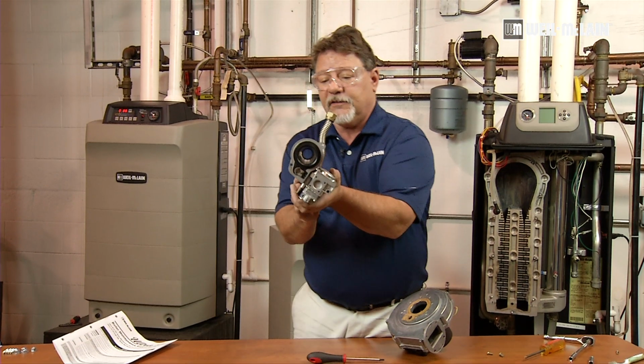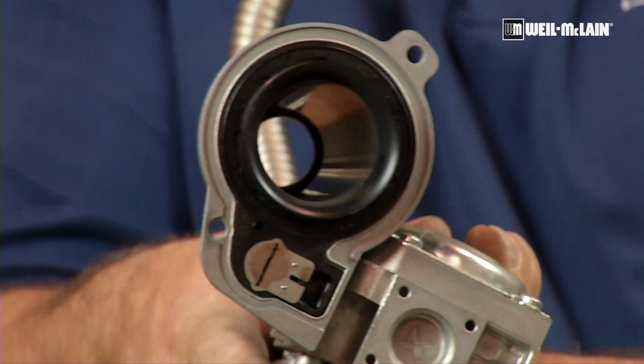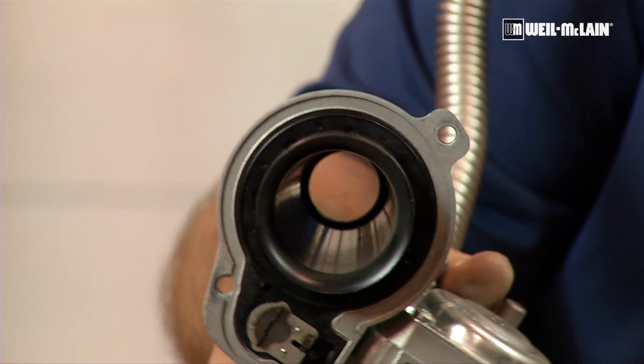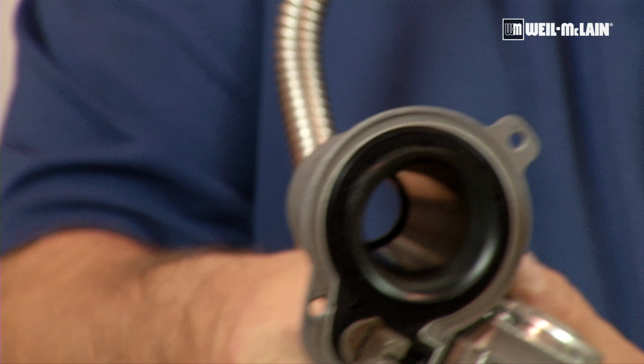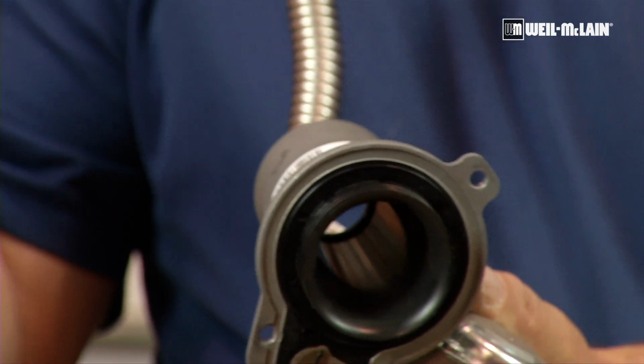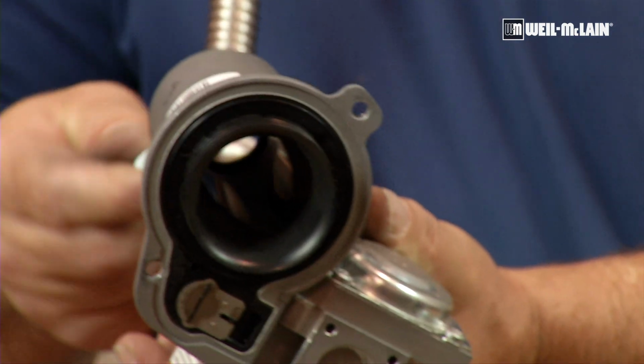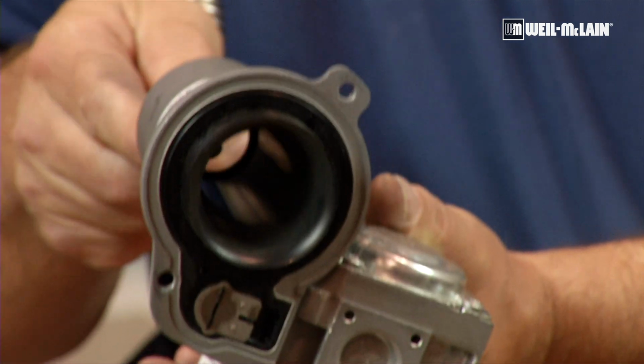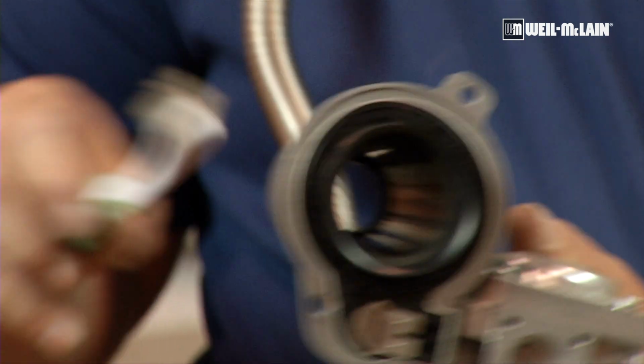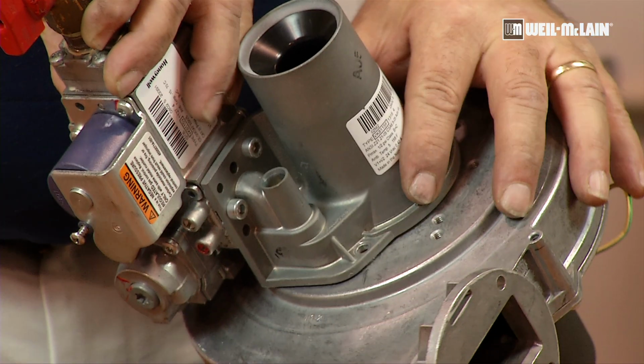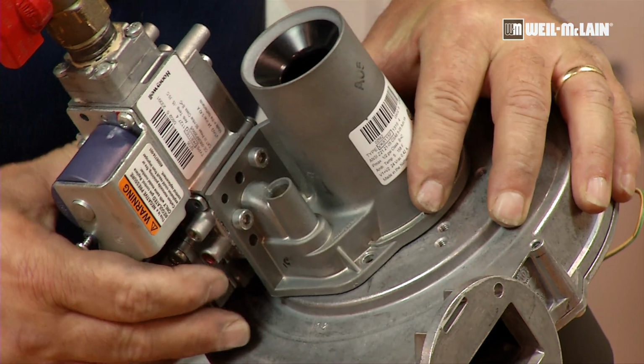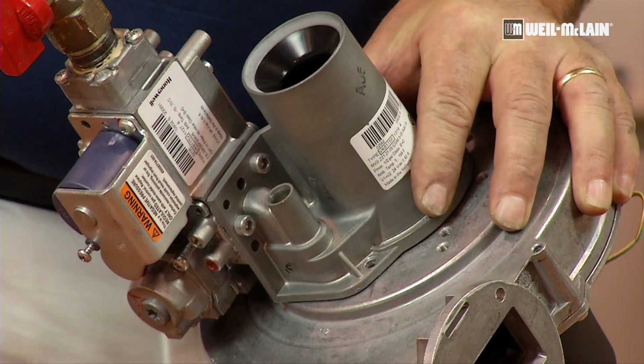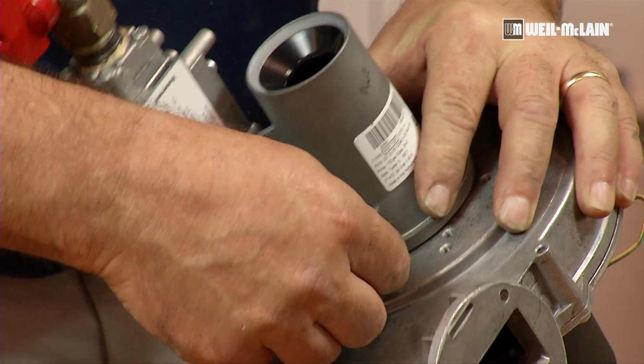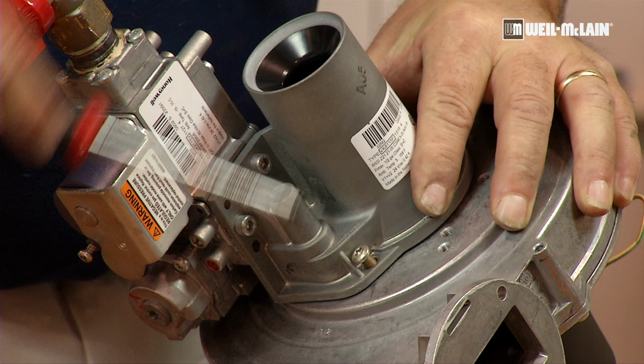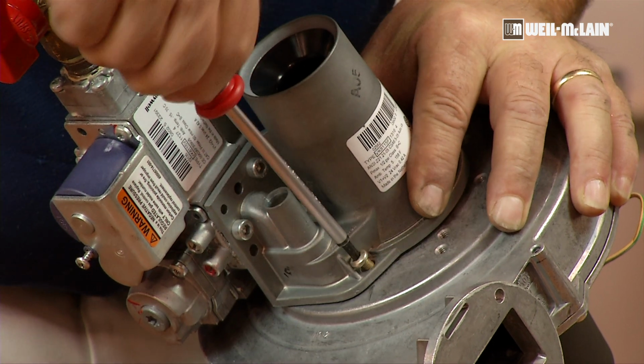If you look inside the Venturi, there is a slot that goes all the way around the perimeter of the Venturi. So we take a small, again, non-metallic bristle brush and we clean out that slot. I'm going to reinstall the Venturi onto the blower. Again, I'm not tightening that screw all the way at this point until I've located the other one.